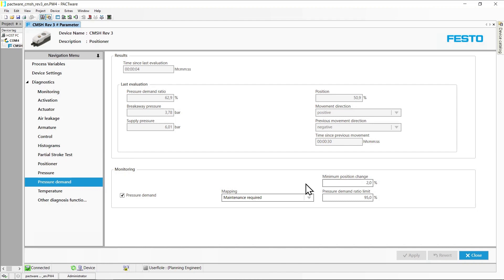The function pressure demand monitors actuator pressures with regard to breakaway behavior. The evaluation is started whenever a new movement is requested by a setpoint change after a period of constant position.